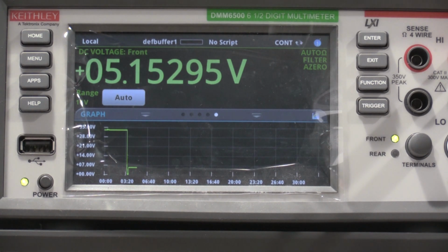Now I need to do the R215 measurement or adjustment, which is the 100 volt regulator. That is for the main calibration. I need to shunt the meter with the 1 megohm because these meters have 10 megohm. So let me get that set up and I'll be right back.